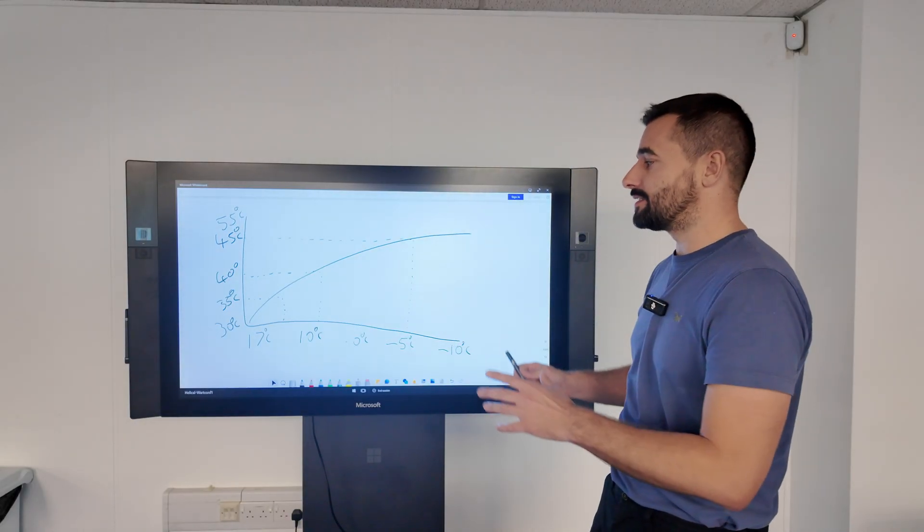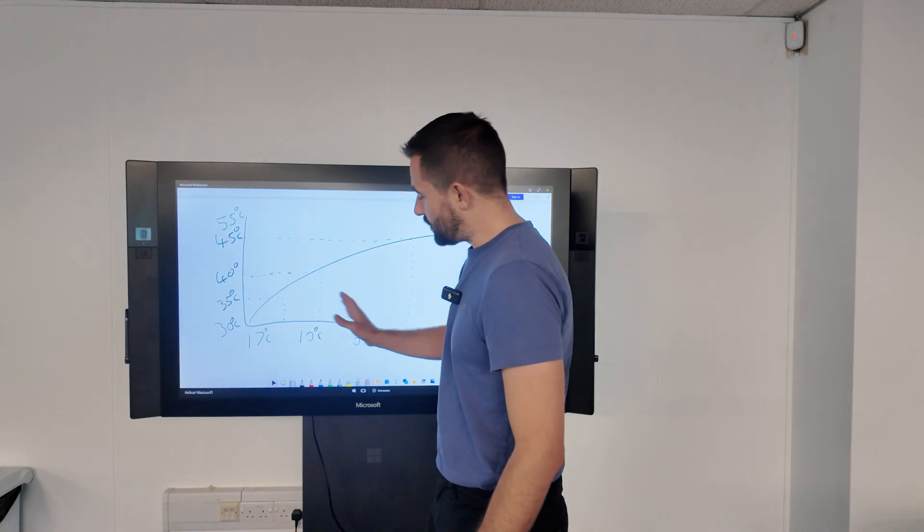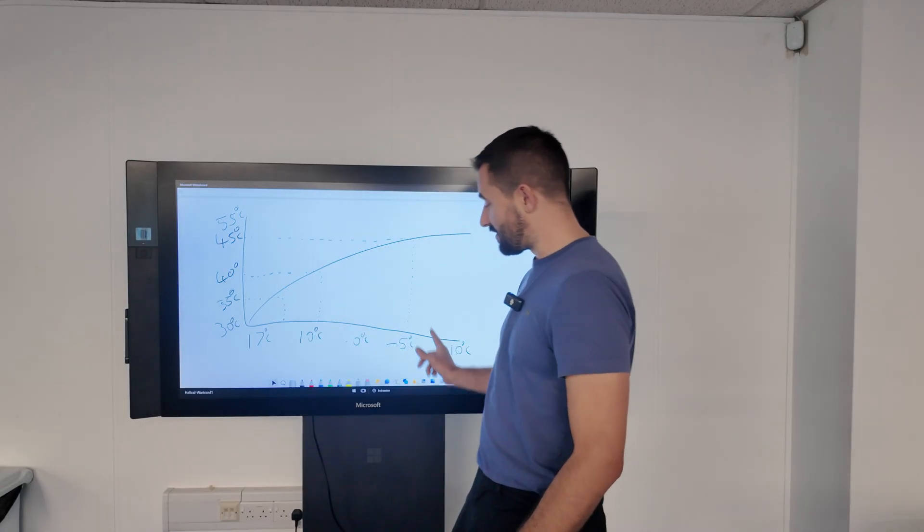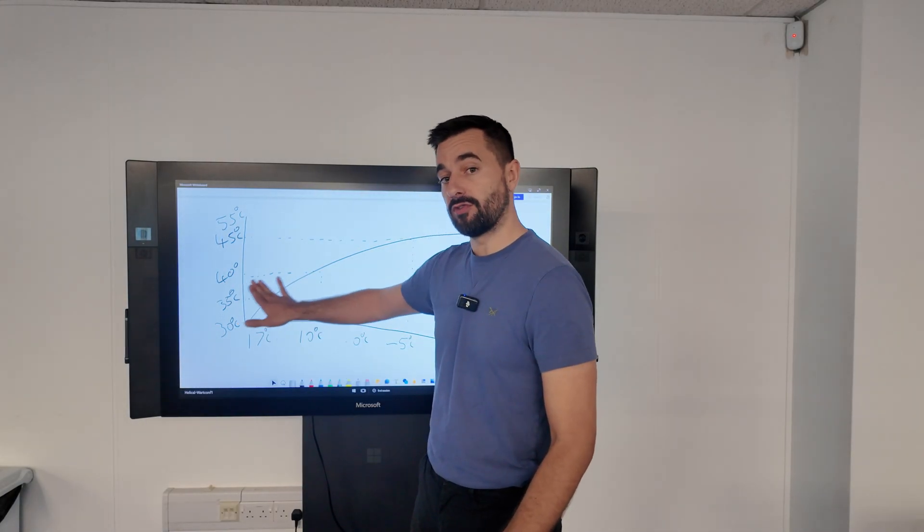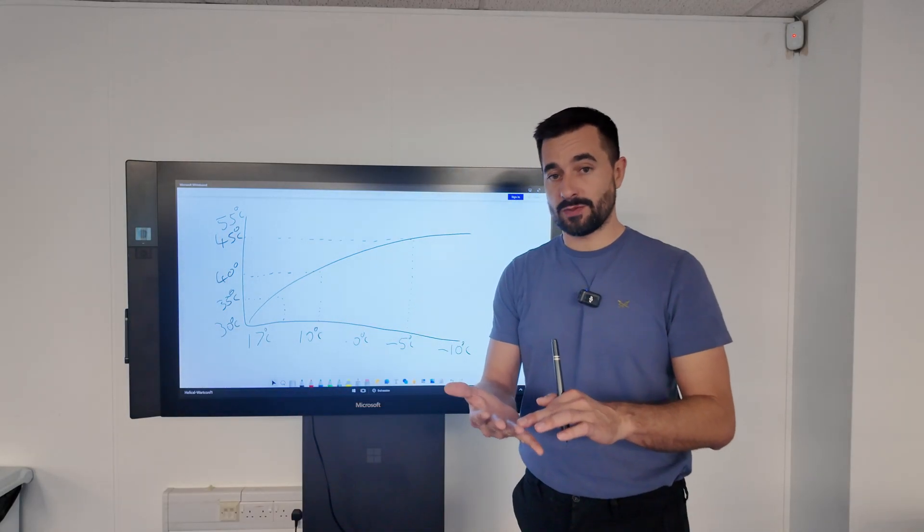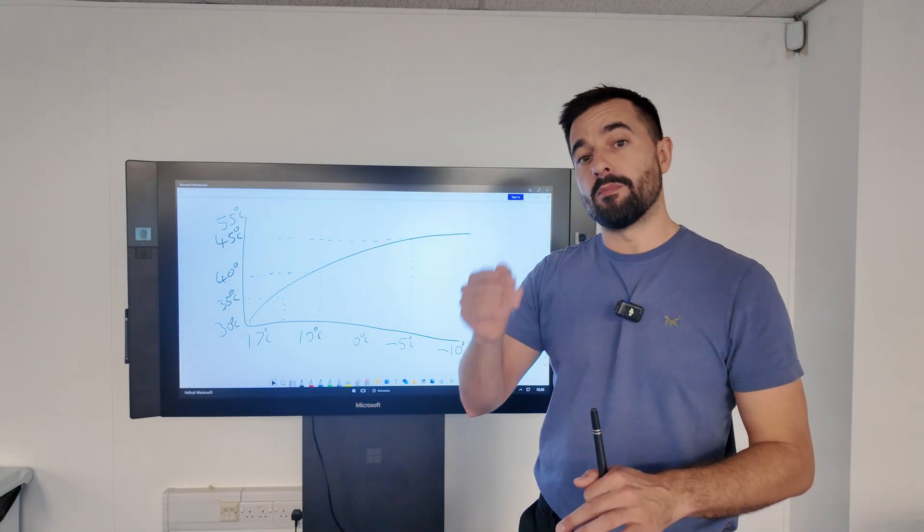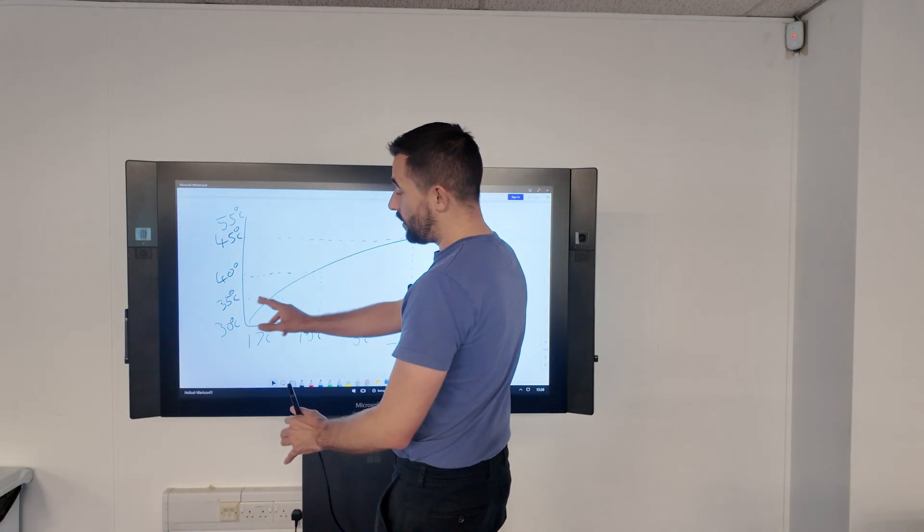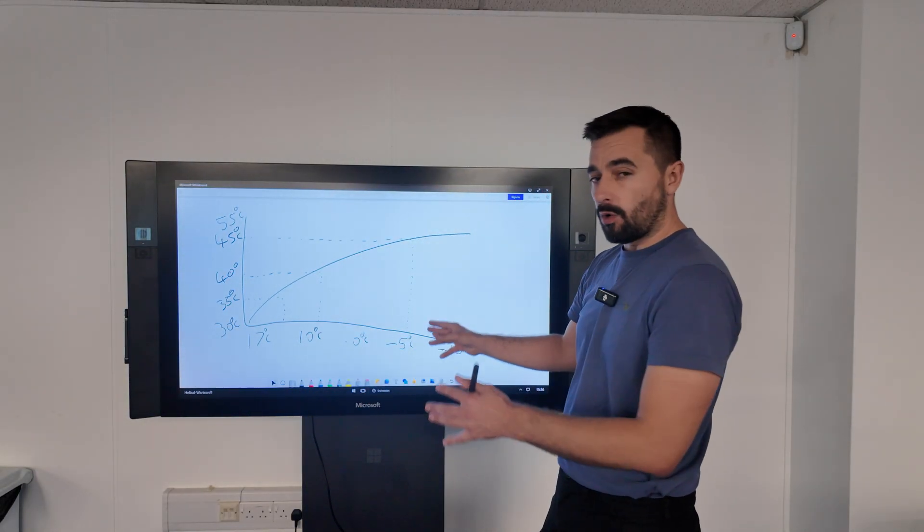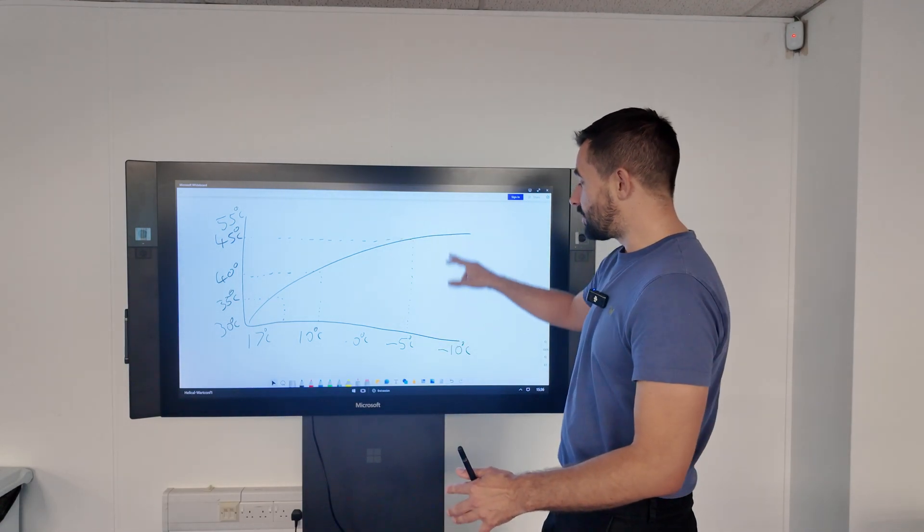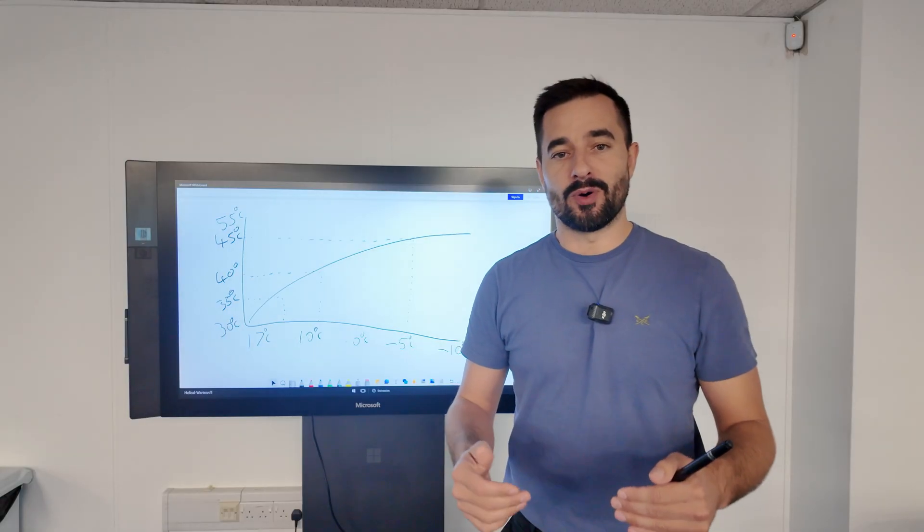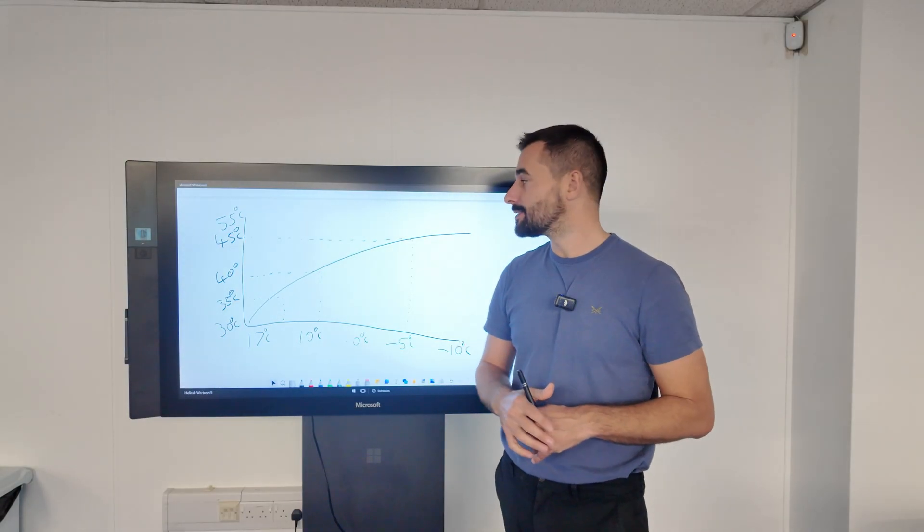The beauty of this is because on average in the UK the winter weather is warmer than the design conditions, for the majority of the year we're running at these low flow temperatures. And with a heat pump and a gas boiler, the lower the flow temp, the more efficient it is. So for vast swaths of the year we're down here. It's only rare conditions—one week of the year, two weeks of the year—that we're having to run at these higher flow temperatures. So we can make that efficiency of the heat pump much better. I hope that makes sense.